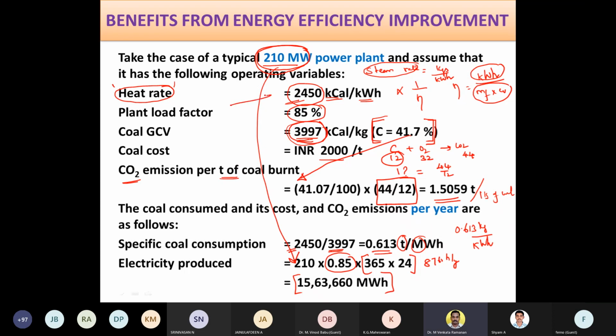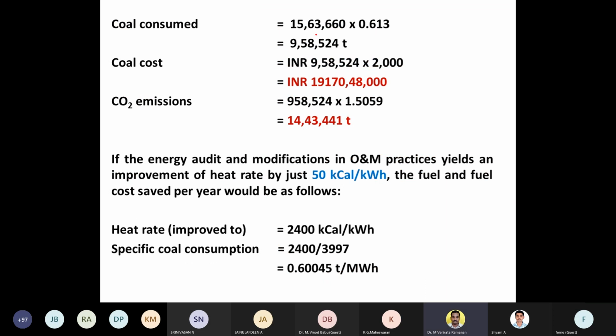Heat rate is one important value to have in mind, like 2,450 kilocalories per unit of electricity. Now, with the amount of power generated and the coal required per megawatt hour in tons, if you have these two factors, you can calculate how much coal has to be supplied. Approximately 10 lakh tons of coal is required for operating a 210 megawatt power plant.